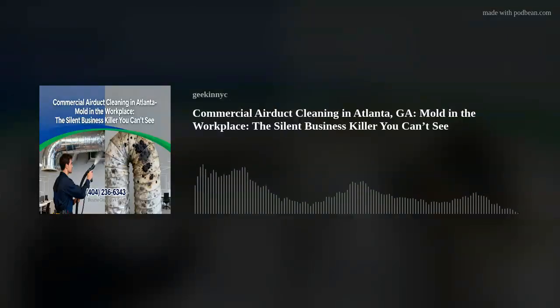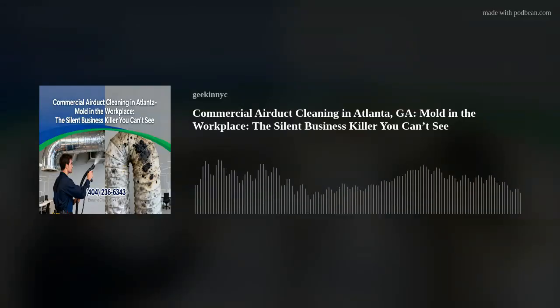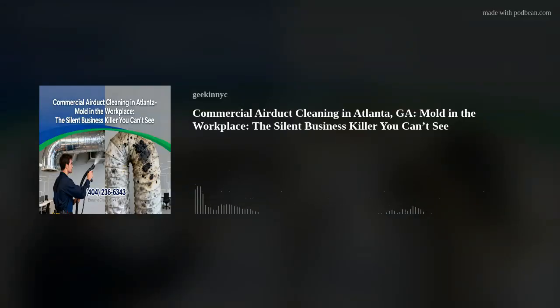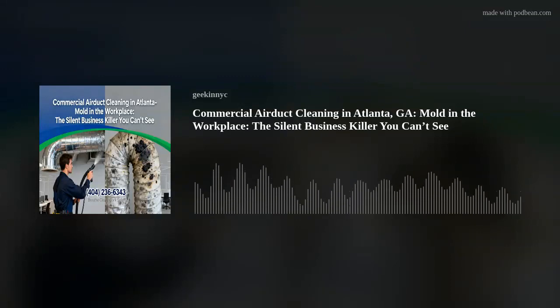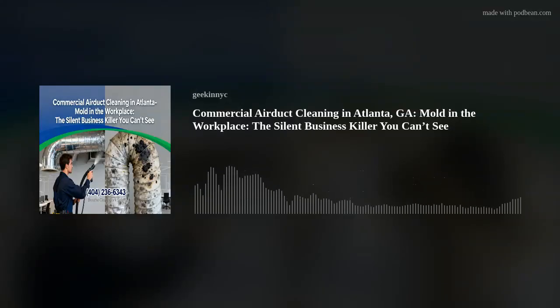To actually protect a commercial system, you have to upgrade to high-capacity media filters. These are massive 4-inch or 5-inch thick filters with deep pleats. And the sources mention these filters have MERV ratings between 11 and 16. What does MERV actually mean? It stands for Minimum Efficiency Reporting Value. It's the industry standard for rating how effectively a filter traps microscopic particles.